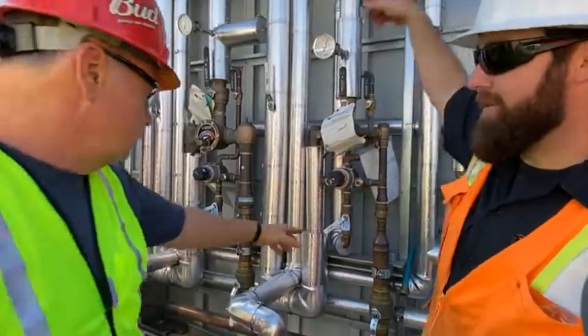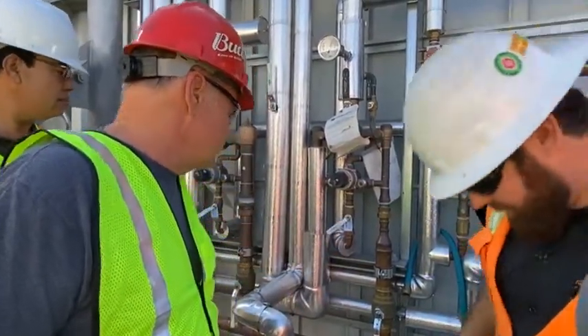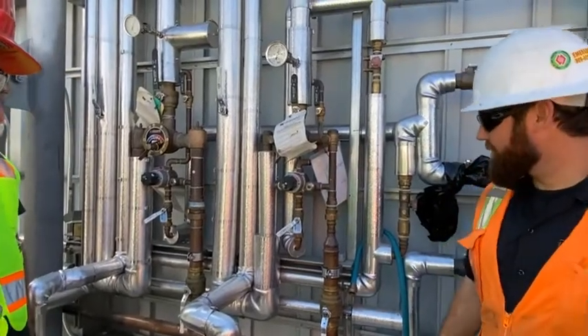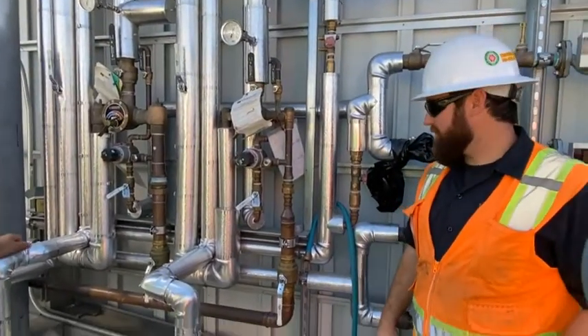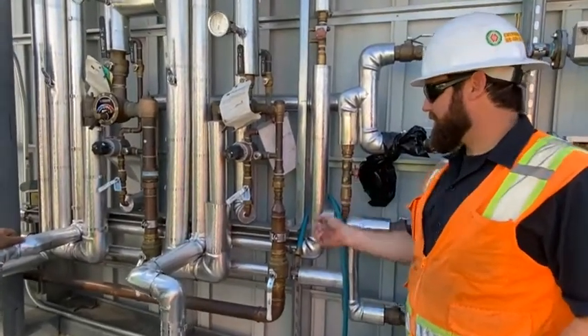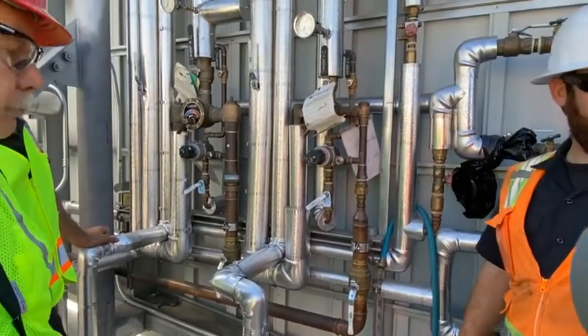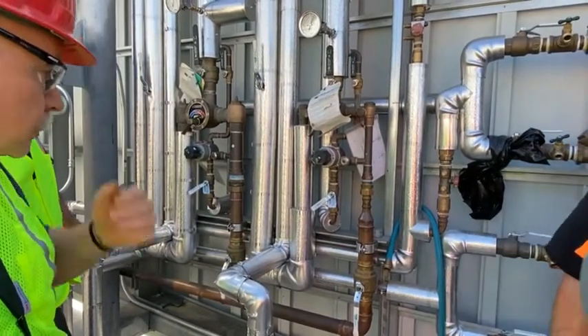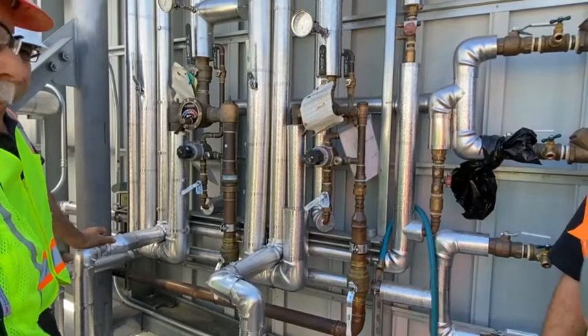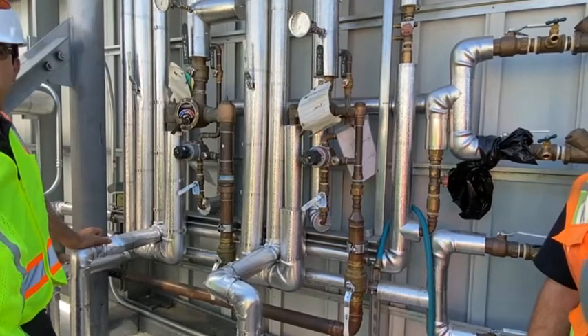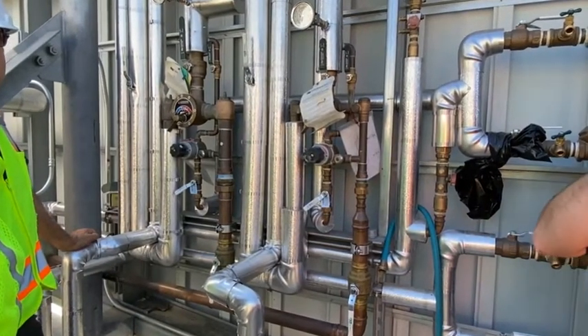You've got mixing valves going out to the system. Yeah, those are the mixing valves. That's the water coming back in the mixing valve. I'm going to try to switch out those ball valves for circuit setters so we can make adjustments. They don't need to be, but I'm going to try to do that. That was part of our training yesterday, but just real quick, the circ pump is pumping water back through the mixing valve and out to the system.